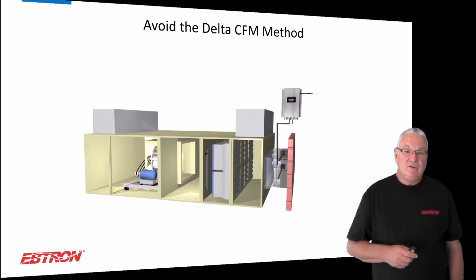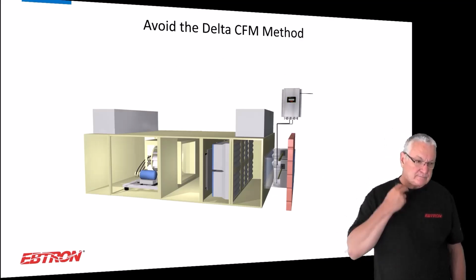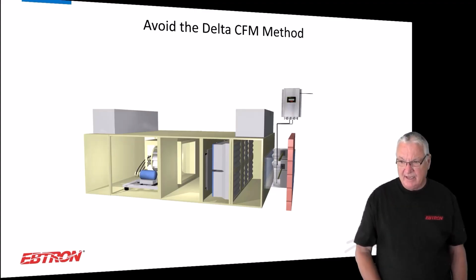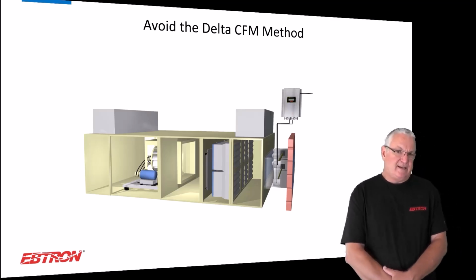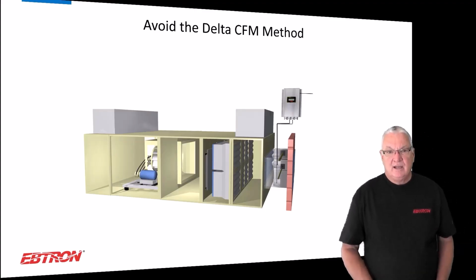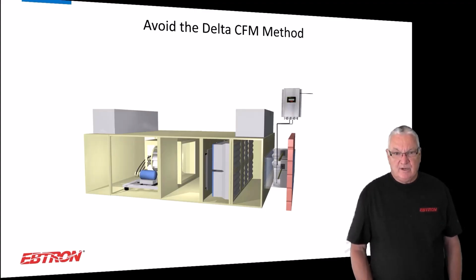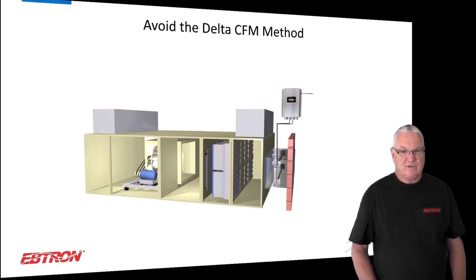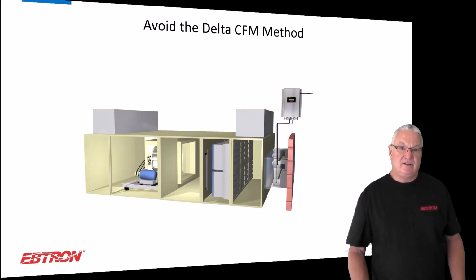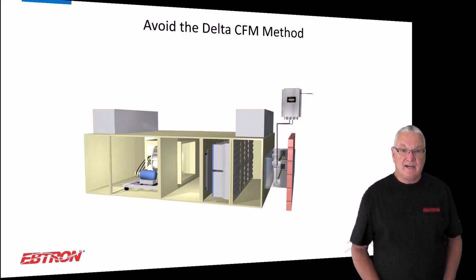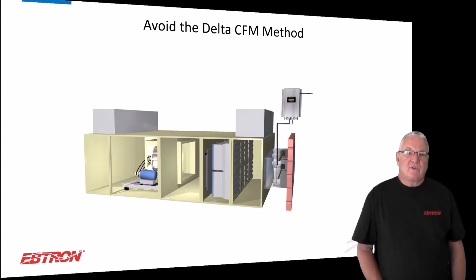The one that gets used a lot, and it really bothers me, is used because a lot of folks will say, well, my air handler comes with piezo rings, and I have supply measurement, I have return measurement. I'm not showing a return fan here, but I see a lot of this, where we take the difference between the two, and that's how we determine our outdoor airflow rate. You're not going to do that if you have relief at the air handler, but if you don't, you can do that, or use it at least to set things up, at least in theory.